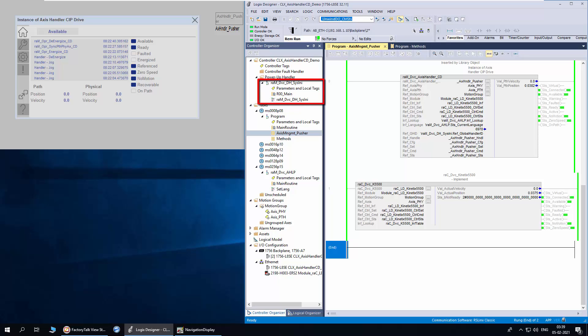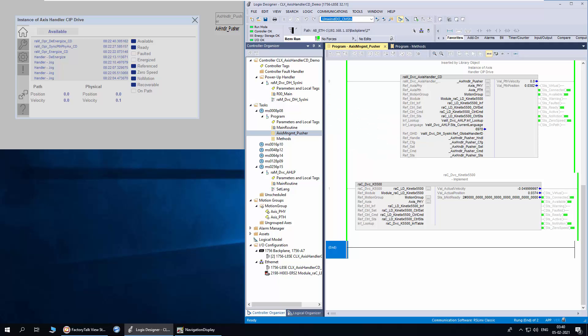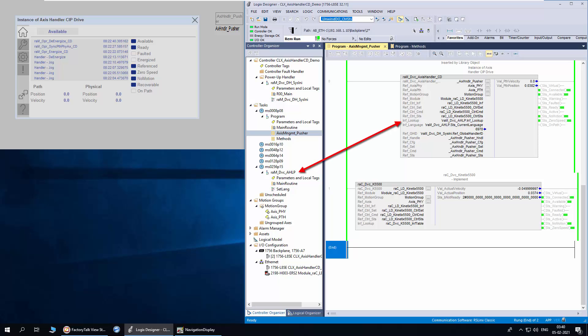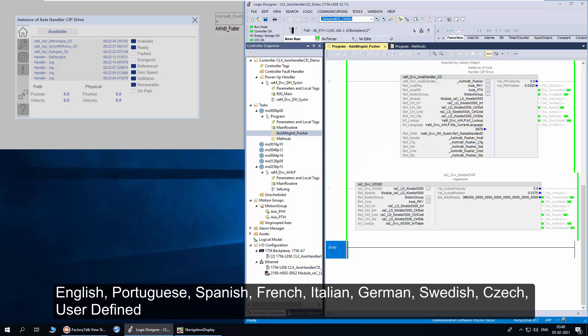System initialization is a program folder scheduled under the controller power-up handler. One instance of the program is required per controller. It provides management of the global handler ID number at controller power-up. Each handler is provided with a unique ID which is used in event capture and also to pair method and handler. Language pack is a program folder — one instance is required per controller. It provides language management for all handler unit messages. English is provided as the default language, but other language add-ins are also available. User-defined language is also allowed provided it is compatible with ASCII characters.